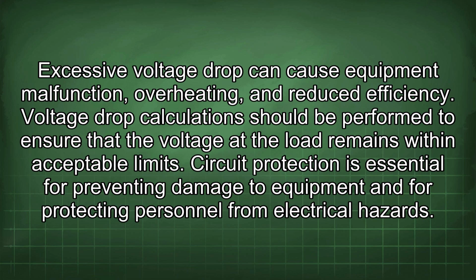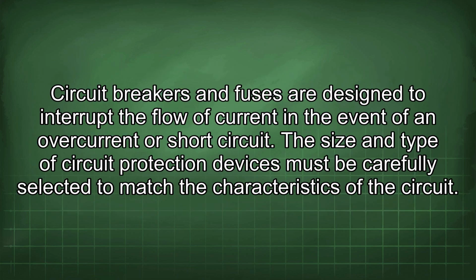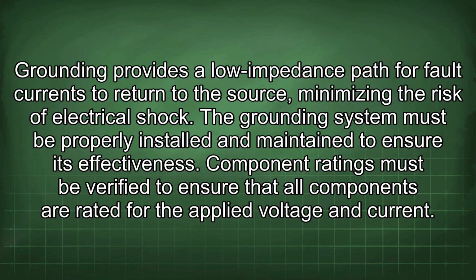Circuit protection is essential for preventing damage to equipment and for protecting personnel from electrical hazards. Circuit breakers and fuses are designed to interrupt the flow of current in the event of an overcurrent or short circuit. The size and type of circuit protection devices must be carefully selected to match the characteristics of the circuit. Grounding provides a lower impedance path for fault currents to return to the source, minimizing the risk of electrical shock. The grounding system must be properly installed and maintained to ensure its effectiveness.